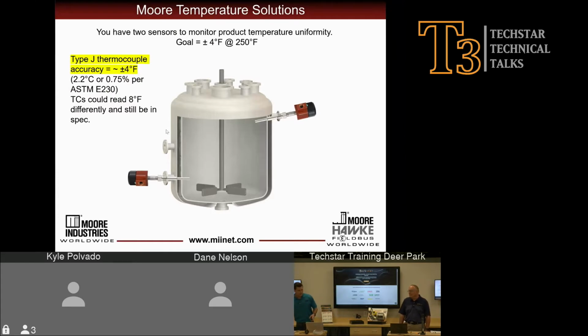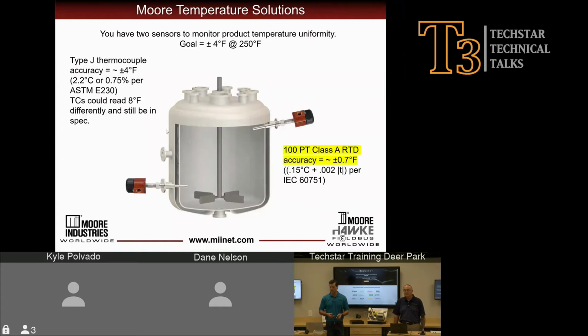So right out of the box, these thermocouples, using 2 of them for this measurement, are not going to yield accuracy and be within the production team specification of plus or minus 4 degrees Fahrenheit. So right out of the box, we're not able to achieve this. So we can do a few things in order to obtain an acceptable tolerance for this temperature measurement. We can calibrate our sensors to transmitters to reduce the uncertainty, or perhaps we can choose a different sensor entirely that better fits the application.